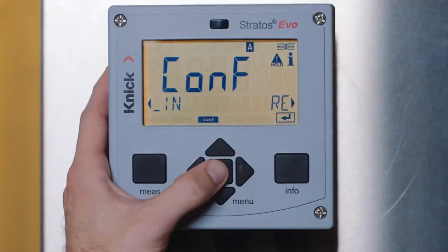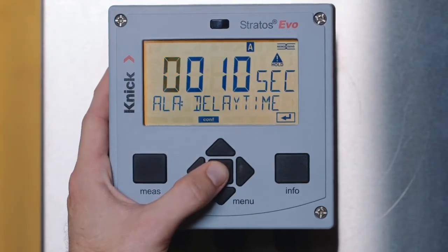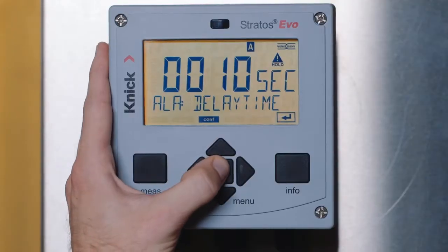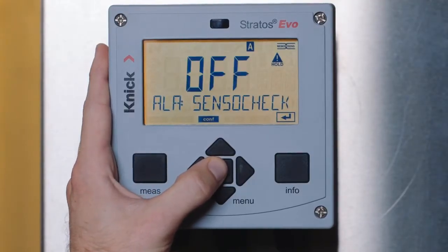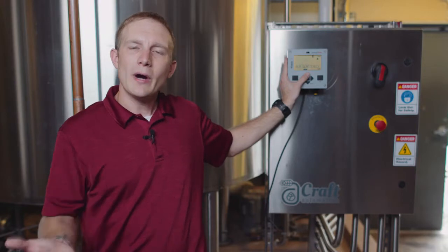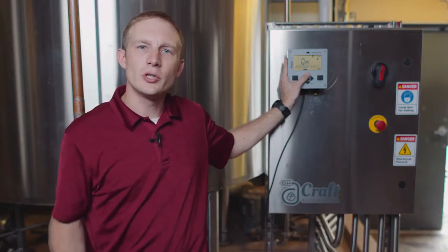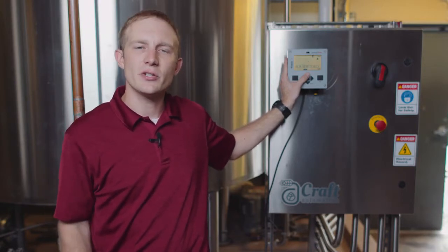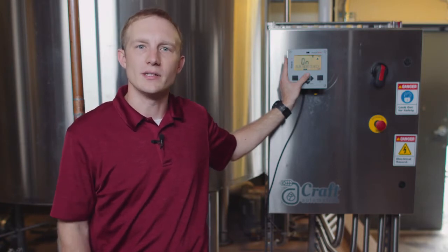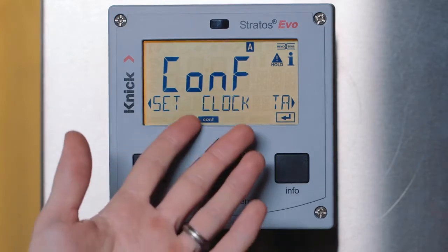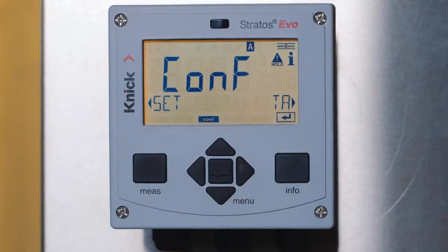Let's select alarm. You will see that you can now define a delay time before the transmitter goes into an alarm mode. We will select enter for a 10-second delay. Next, you will see the SensoCheck feature. We recommend turning this feature on for more intuitive diagnostics, such as the SensoFace indicator, as well as additional icons which refer to specific errors. Lastly, the clock menu is a very important menu to configure. Doing so ensures proper information is written to the connected Memosens sensor.